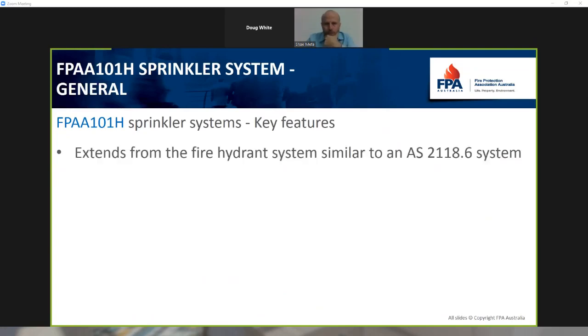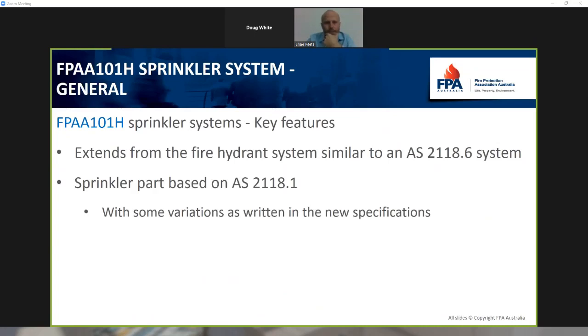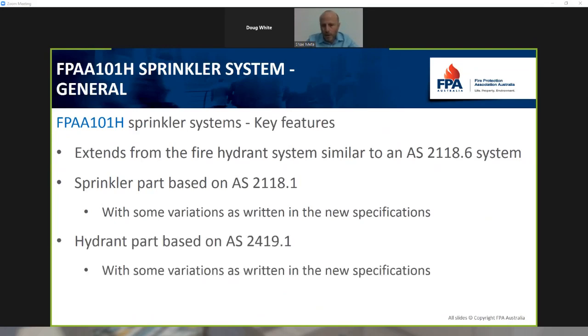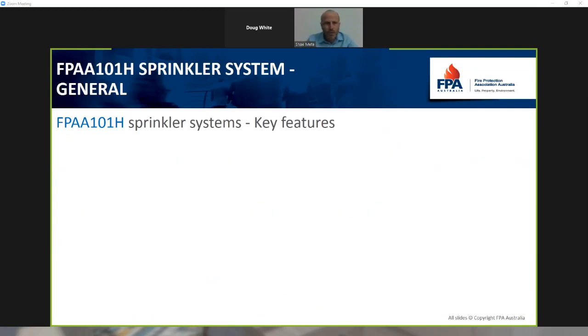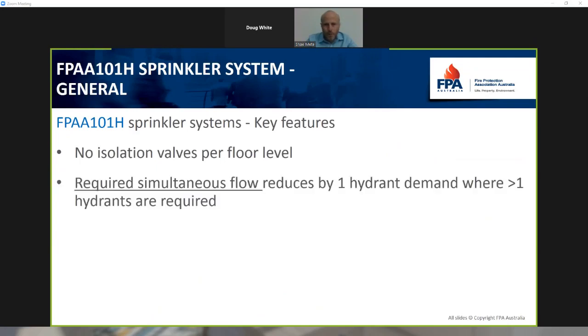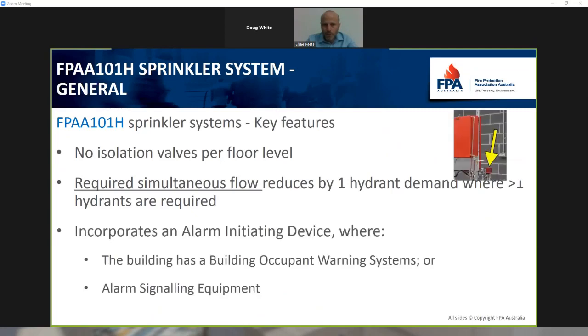Some of the key features for the 101H: it extends from the hydrant system, very similar to 2118 Part 6. The sprinkler part of the building is essentially entirely based on 2118 Part 1. It relies on those clauses, and the hydrant system falls back to 2419 Part 1. So you can always think of this as 2 separate systems, 2118 and 2419, combined together in the same way as a Part 6 building typically is. No isolation valves per floor. It requires, we'll talk about that in the next slide. I think we'll just try and get through this.